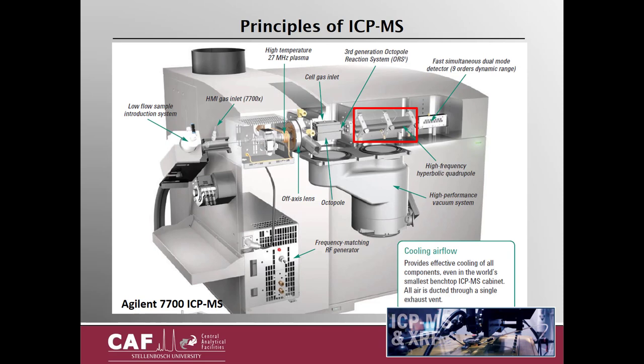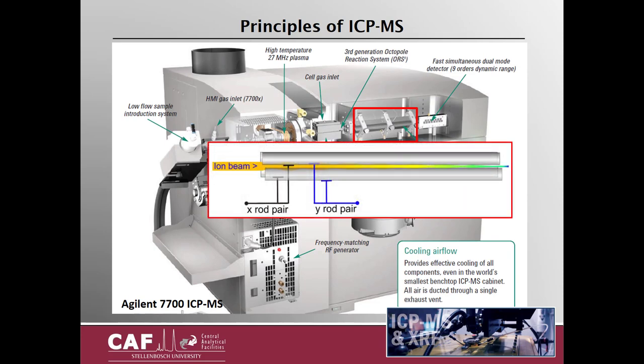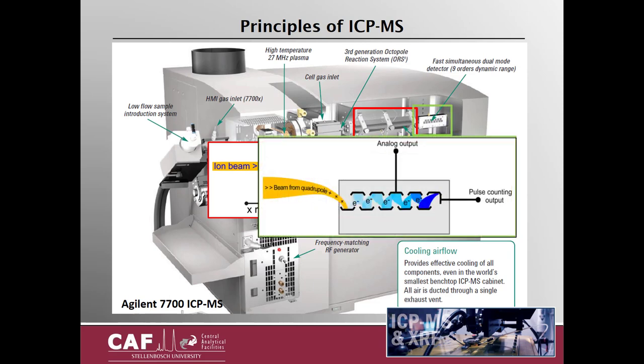After the interfering molecules have been removed in the collision cell and the analytes exit, they pass through the quadrupole mass analyzer where different voltages are applied that stabilize only a single isotope mass at a time and pass it onto the detector. It is therefore a very fast sequential process, with measurement for laser ablation typically at 10 milliseconds per isotope mass.